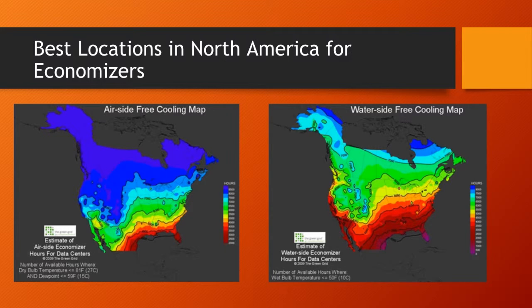The main reason air side is more efficient is because air side is using the direct air, taking it right from the outside through the air duct into the building. The water side has to run it through that heat exchanger. Every time you run water or heat through a heat exchanger, there is a little bit of loss to it. So the reason a lot of green is here, that's just showing physical heat exchanger loss. And in some buildings, they're okay with that because they can only use a water side economizer. But a lot of buildings, you're going to see air side economizers strictly because they can get more hours out of it for their location.